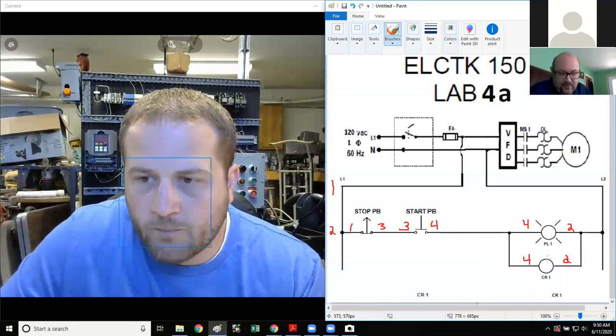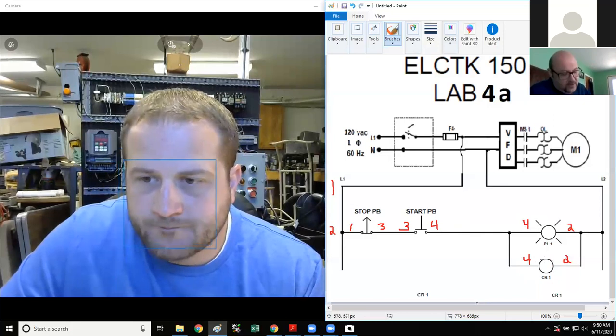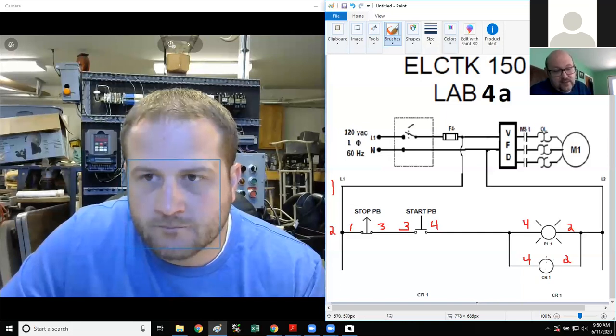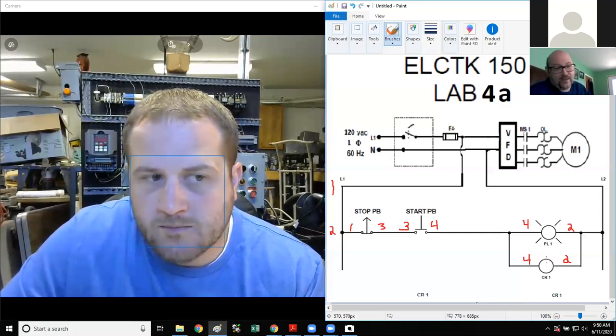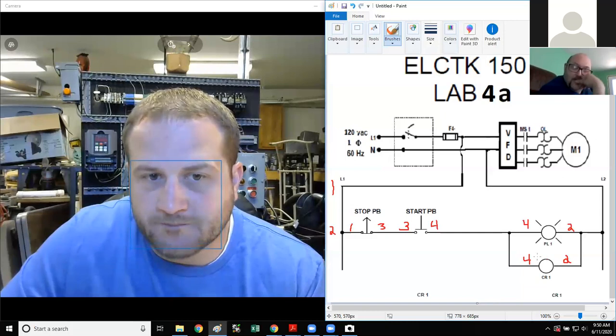And that's what drives me nuts, because every time I go to look for something, I think it was a different wire number, but it shows it's connected in parallel. You never know how they connected it in parallel. You don't know if they connected it directly off the start push button, or if they went 10 feet down, spliced into the line in a junction box, and then brought it down to that control relay. It would drive me absolutely nuts.